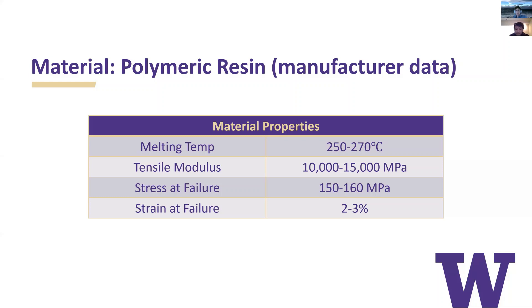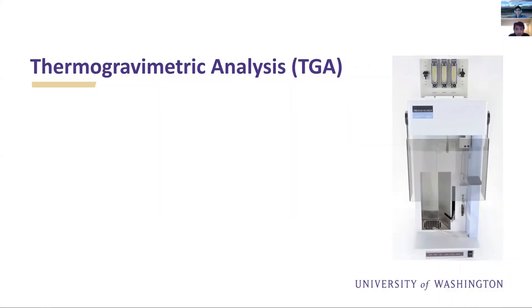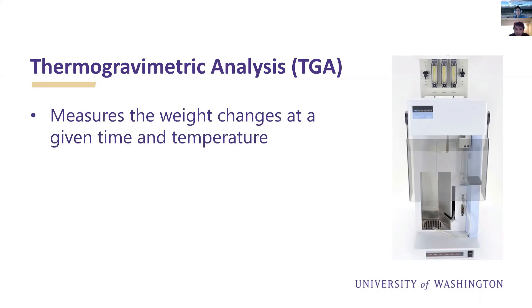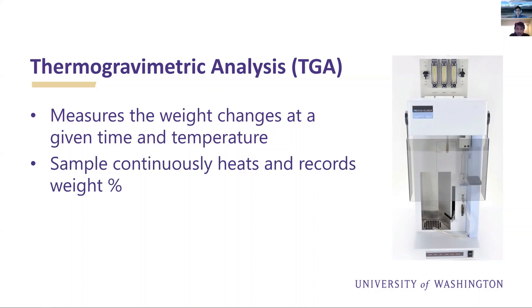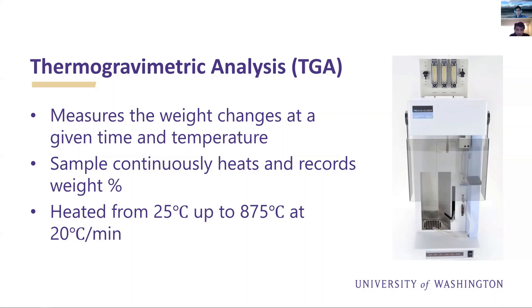I'm going to hand you over to Elijah, who's going to go into our analytical tests. To begin, we'll start with the thermogravimetric analysis, or TGA. You can see to the right a diagram of a TGA used for testing. The TGA mainly measures the weight changes at a given time and temperature. As our sample continuously heats, the weight percent is recorded — the sample is either hanging on or sitting on top of a scale. As the temperature increases, the material degrades, causing the weight percent to change. Typically, it's heated from 25°C to 875°C at a rate of 20 degrees Celsius per minute.